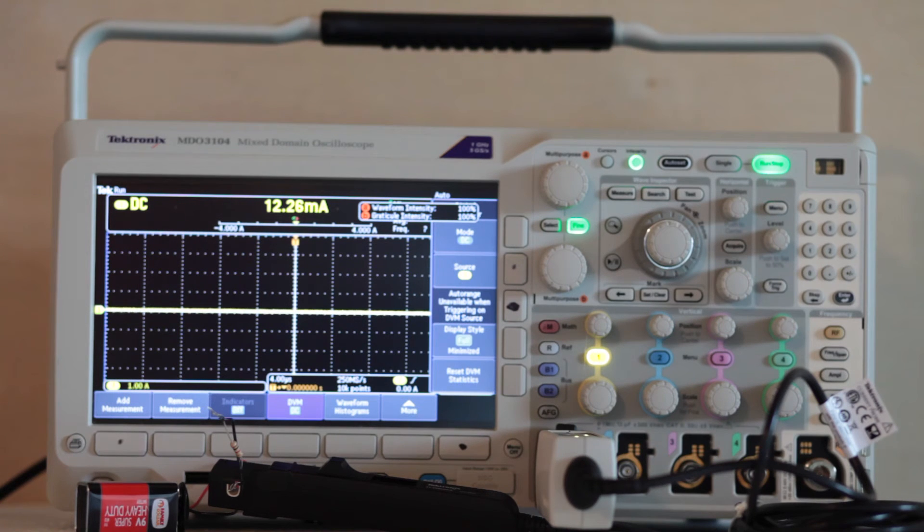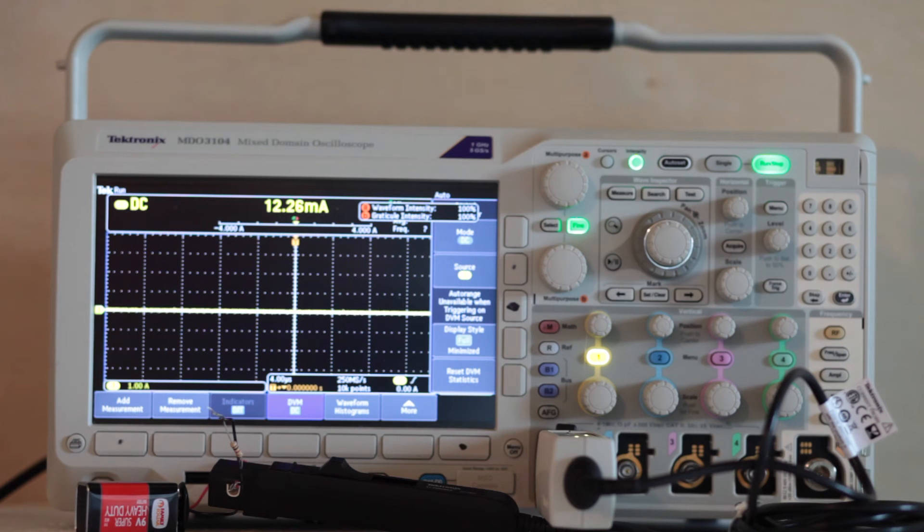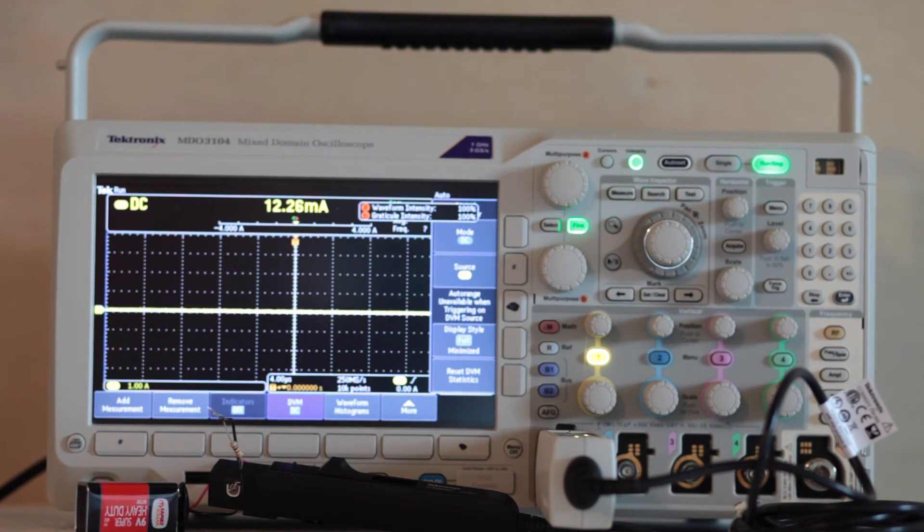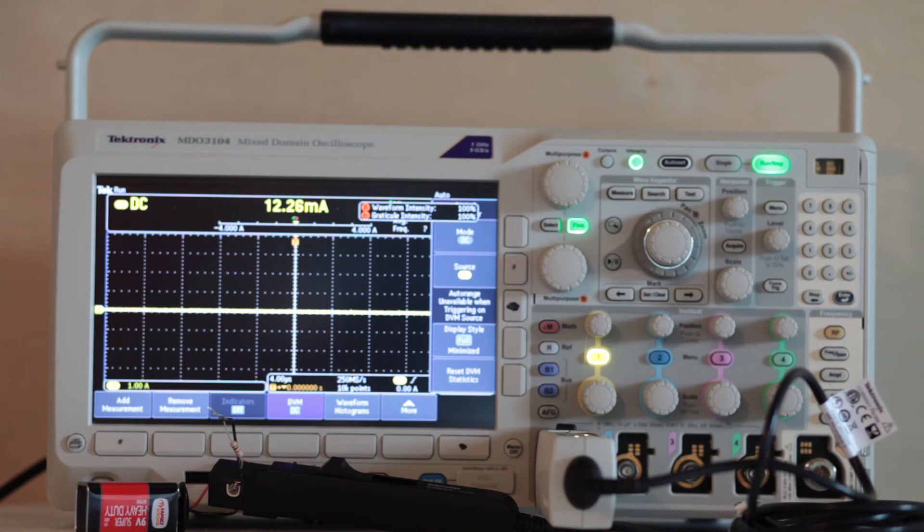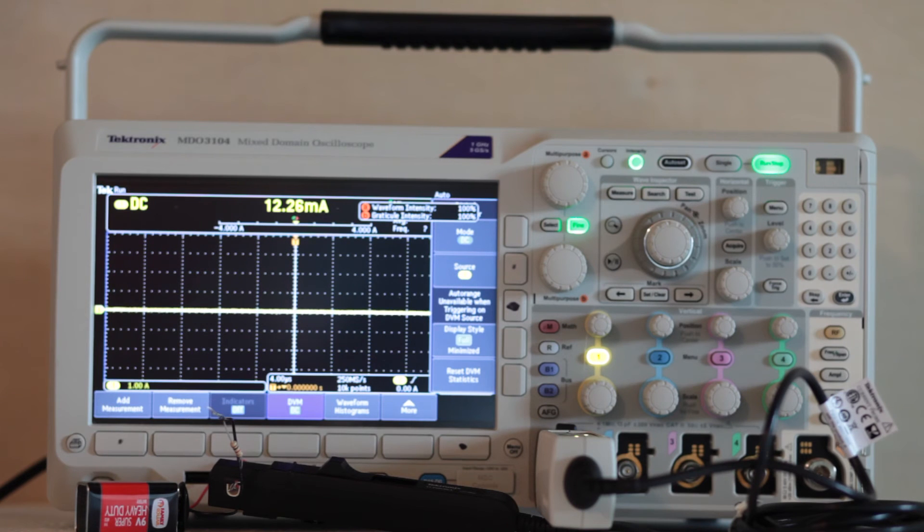The Tektronix TCP-0030A current probe is essentially a clamp-on ammeter. It is very sensitive, and as a consequence, it has to be degaussed periodically. This is because the jaws can act as a permanent magnet and become magnetized.